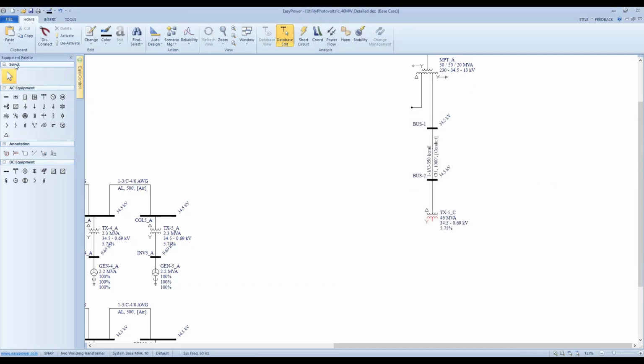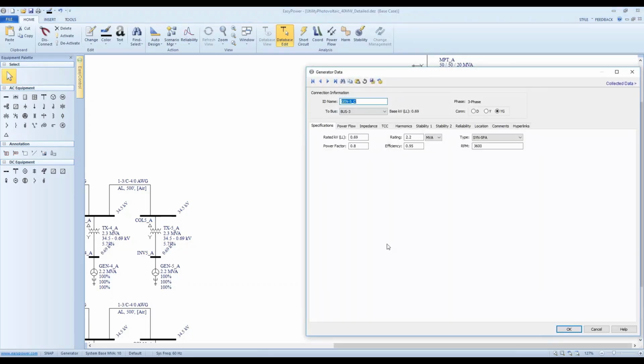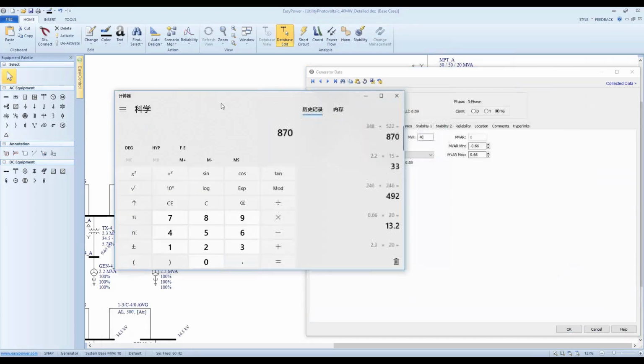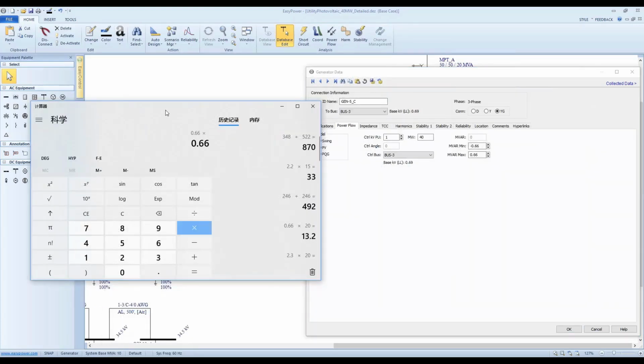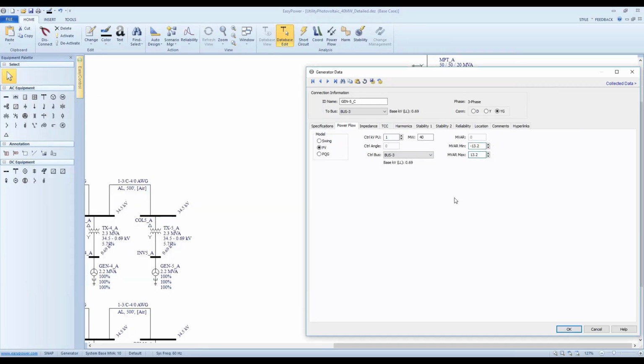Okay. And then I put another bus here. Copy this generator here as well. I don't have to touch anything to my synchronous transient and subtransient impedance at all. All I need is just to raise the MVA by 20 times. That's 44. And my power flow, change this to 40. Now I do need to change the reactive power as well because that's 0.66 multiplied by 20 times, which would give me 13.2. Okay, so I have negative 13.2 and positive 13.2. Right? Is anything wrong? Guess not.